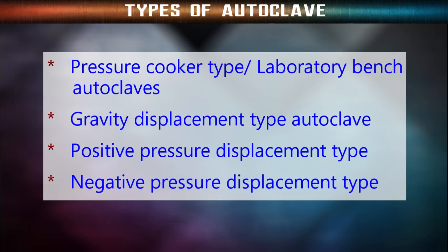Next is the negative pressure displacement type. This is another type of autoclave which contains both a steam generator as well as a vacuum generator. Here, the vacuum generator pulls out all the air from inside the autoclave while the steam generator creates steam. The steam is then passed into the autoclave. This is the most recommended type of autoclave as it is very accurate, and this is also the most expensive type of autoclave.